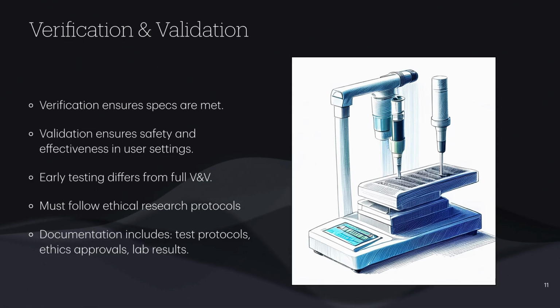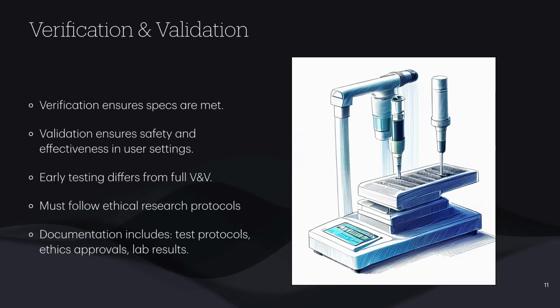Before a device can be mass-produced or submitted for regulatory approval, it must pass rigorous testing. This brings us to the verification and validation phase, often abbreviated as V&V. Let's clarify these terms. Verification asks, did we build the device according to the design specs? For example, if the valve is supposed to open at 80 millimeters mercury, does it actually open at 80 millimeters mercury? Validation asks, does the device work as intended in the real world? Does it solve the problem in its intended use environment?